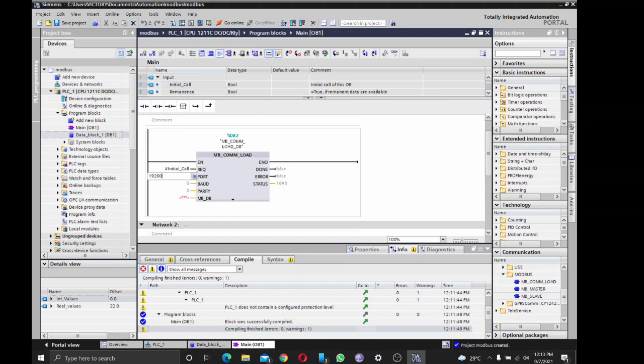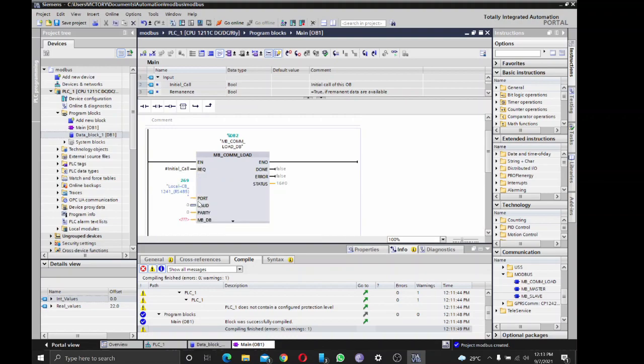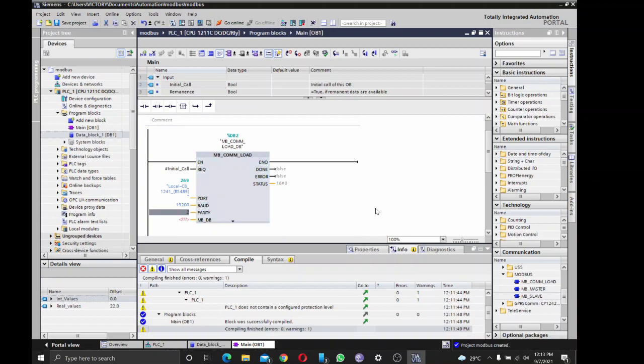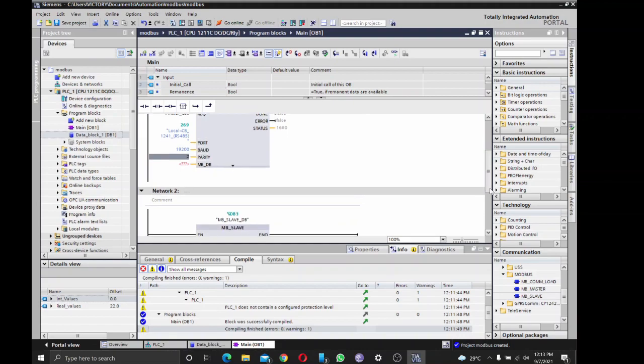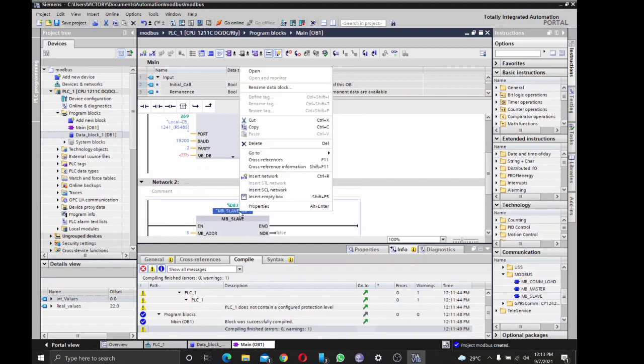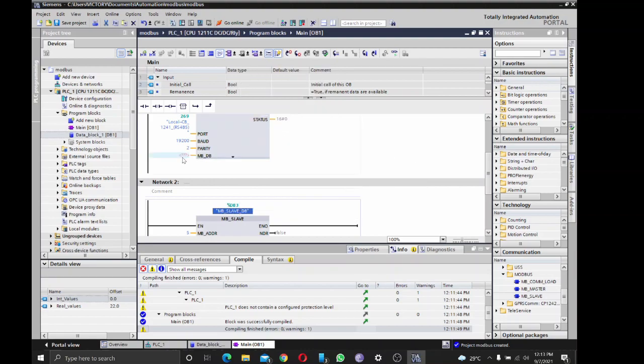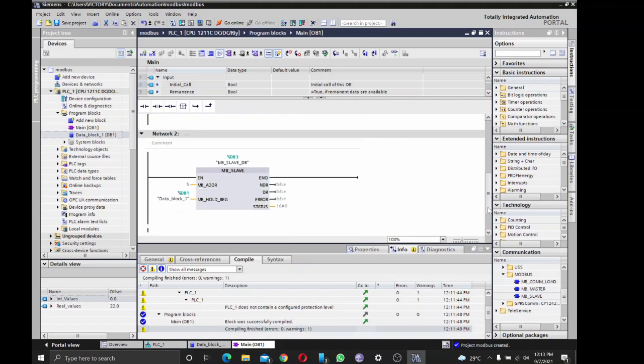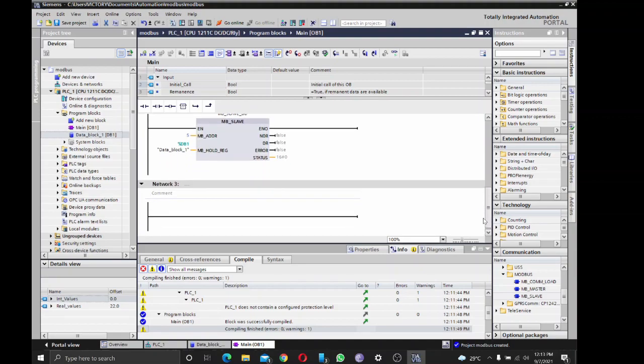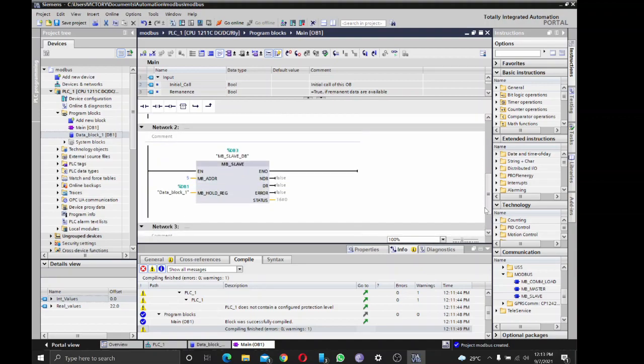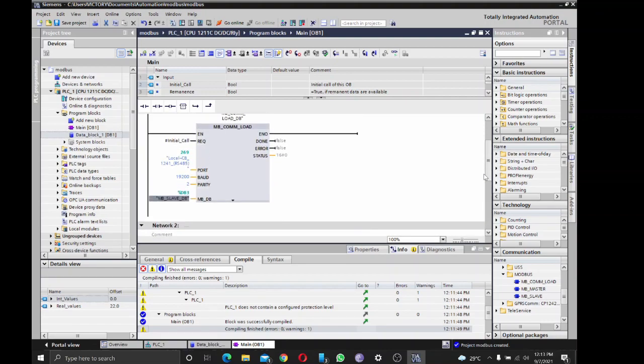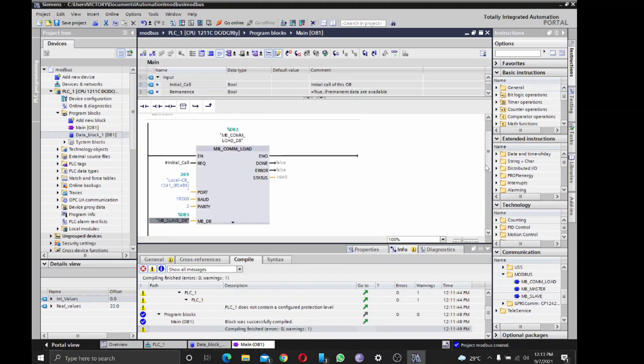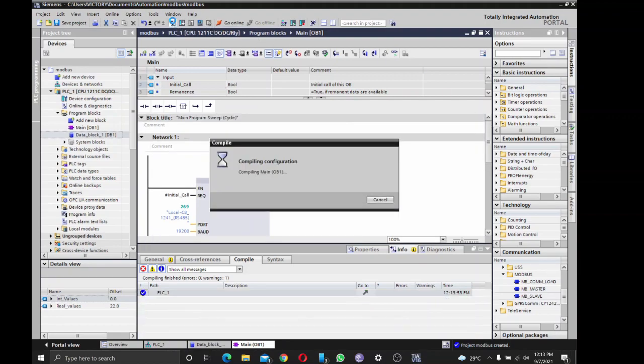Okay, then my request - I'm going to use the initial call which is a temporary variable. My port - these are our ports. Then our baud rate is 19200. Our parity is 2 because even is 2. For Modbus DB, I'll just copy this and paste. So with this, I think we are good to go. I've got my holding register, my address, slave, parity, baud, port. Yeah, I think we're good to go. Compile.